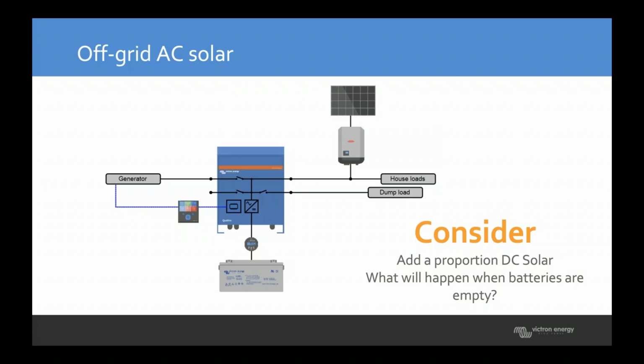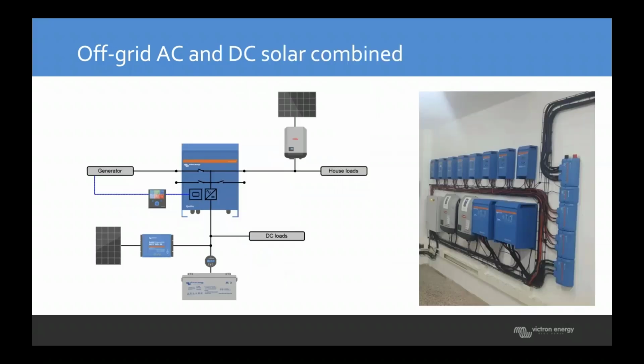In this case, the Fronius depends upon that sine wave that the inverter charger is creating to start up. So you could have an issue where the system gets too deeply discharged and becomes stuck. Now, what you need to do in that instance is provide another source of power. This could be a generator, which you could start up, or you could also add a Victron MPPT on the DC bus.